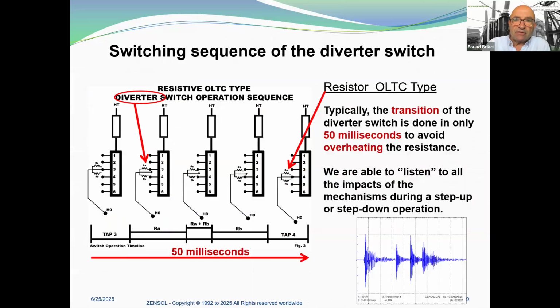Here you have the switching sequence of a diverter switch, so the resistor type OLTC. Here you can see the details of the steps of a diverter switch transition from tap 3 to tap 4. The changeover must be made quickly, in 40 to 60 milliseconds, to avoid overheating the resistance for the resistor-type OLTC. So we are able to listen to all the impacts of the mechanism during a step up or step down operation. Here is the move of the diverter switch in action. And here you have the different steps that we have to go through to do a switching sequence for the diverter.